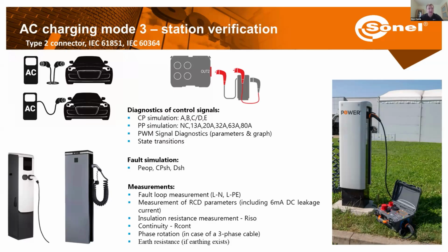Further on, we need to simulate some faults and see how the charger is behaving. And we need to perform measurements. They are kind of similar to regular electrical installations. So we need to check fault loop impedance. We need to measure parameters of the RCDs. We need to check insulation resistance, continuity. In case of three-phase charging stations, we need to check phase rotation, and check the earth resistance of the charging station, but only in case it has earthing of its own. So, for example, when we have a charging station in a building, in some garage, then it's probably connected with the earthing of the entire building. But when we have a charging station outdoors, it may have independent earthing. So in this situation, we need to check the earth resistance of this earthing.